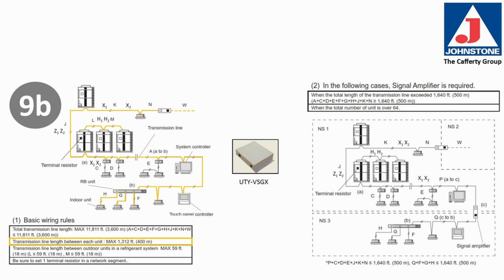Transmission line between each unit maximum is 1,312 feet. Transmission line between the outdoor units in a refrigeration system, maximum 59 feet. Be sure to set one terminal resistor in the network segment. In the following cases, a signal amplifier is required when the total line length of the transmission line exceeds 1,640 feet, or when the total number of units is over 64.